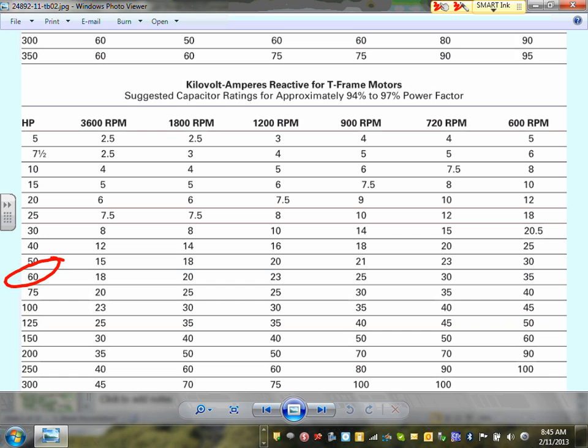And almost always they're running at close to 1800. The synchronous speed is 1800 RPM, and almost always, Jeff, new equipment is T-frame motors. They call them T-frame, the old RU T-frame motors. Almost always you have to correct to these two values, 94 or 97, not 100, okay? And I need to correct the power factor for this.